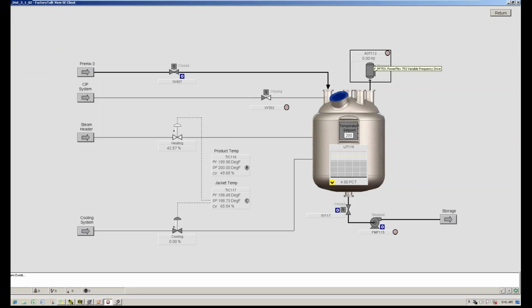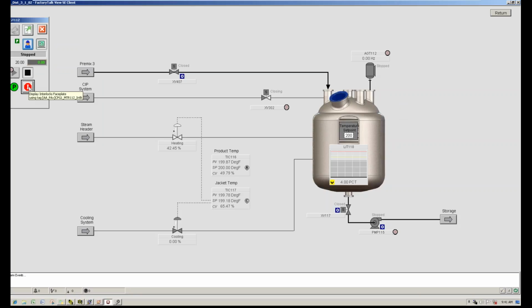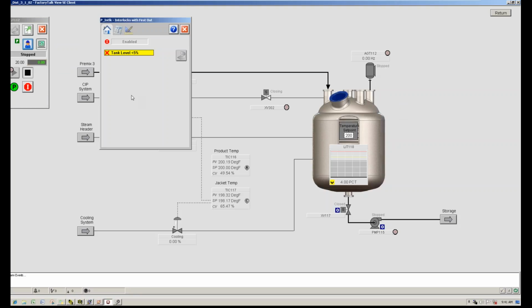here was the interlock. So here I've launched my agitator, and I can't operate the agitator because I've got this interlock condition active. Now just to show you, if I click on that, it takes me to the source of that interlock fault, and it's telling me that because I haven't got any level in my tank, the tank level is less than 5%, I can't operate that agitator. Now, there's a couple of things we can do here. Obviously, we can put more product in the tank until it's above that 5%.